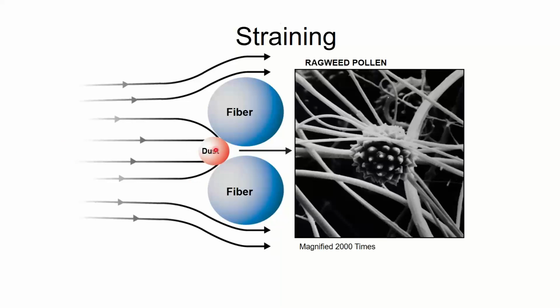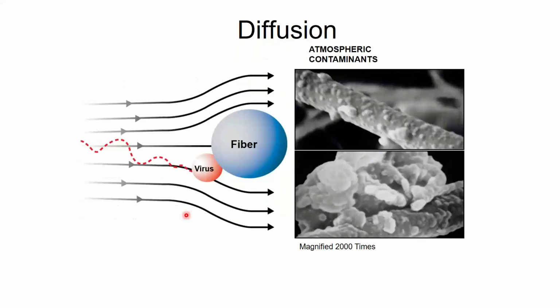Now, as you might imagine, if this piece of dust gets stuck here, that means any dust coming behind him is going to get stuck behind him, even if it's a little bit smaller. The dirtier your filter gets, the better your filter gets at capturing stuff. It's kind of weird, right? We always tell you change your filters, change your filters. The dirtier your filter gets, the better it is at being a filter. However, it's also good at stopping airflow at that point, and that causes all kinds of other problems in our buildings. So we have to change the filters to keep the airflow up, but as far as catching stuff, the dirtier the better, until it breaks or until it clogs up too much airflow.